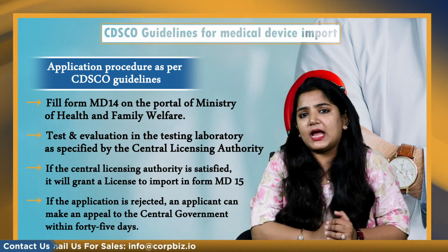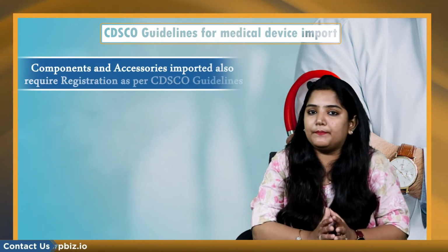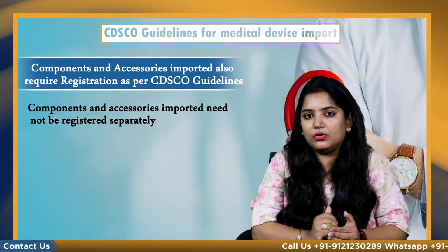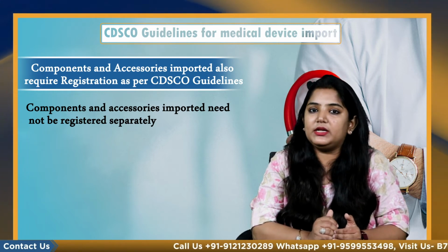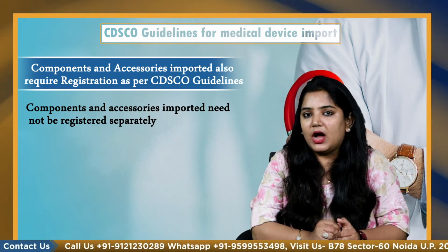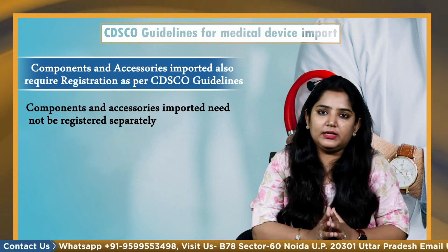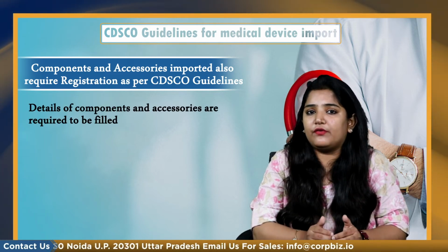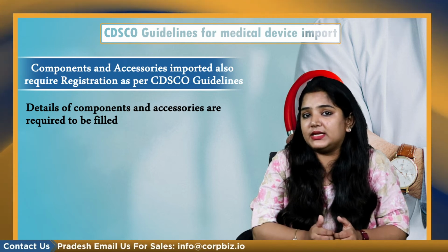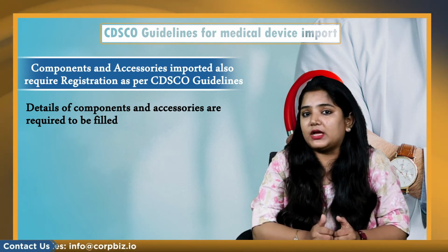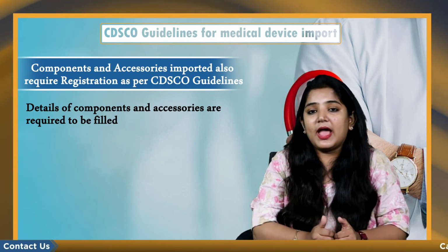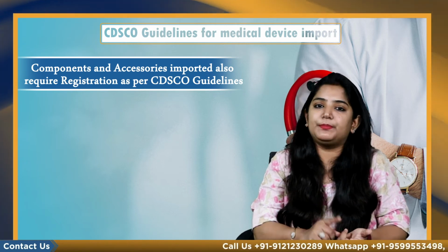Now moving forward, let's understand whether imported components and accessories also require registration as per CDSCO guidelines. As per CDSCO, imported components and accessories need not be registered separately. However, what separately means is not clear. All components and accessories should be registered because in the registration form, details of components and accessories are required to be filled in. If any components and accessories are not registered as a medical device for some reason, then they need to be registered as a medical device as per the definition mentioned in the Act.